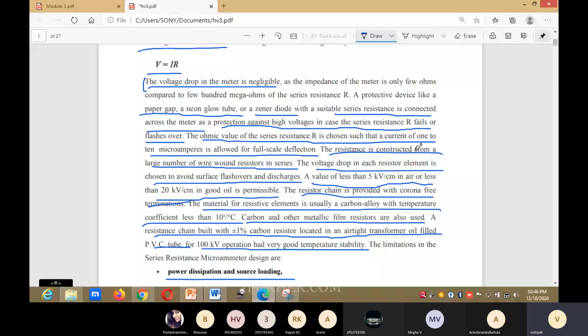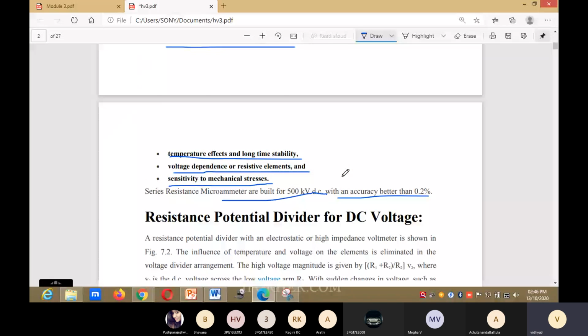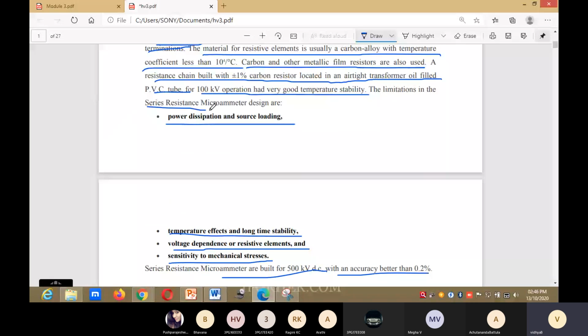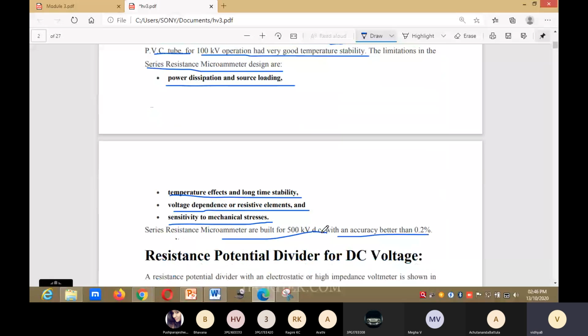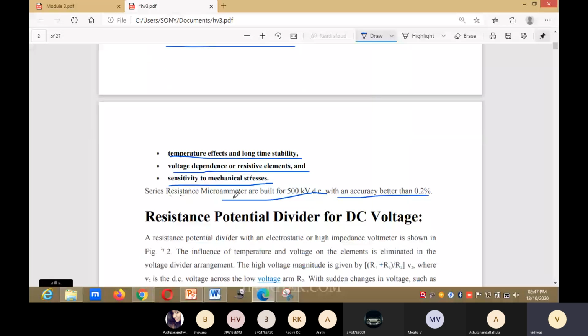The resistance is constructed from a large number of wire-wound resistors in series. And the limitations of the series resistance microammeter design are power dissipation and source loading, temperature effect and long time stability, voltage dependence of resistive elements, and sensitivity to mechanical stress. They are built for 500 kV DC with an accuracy of 0.2%.